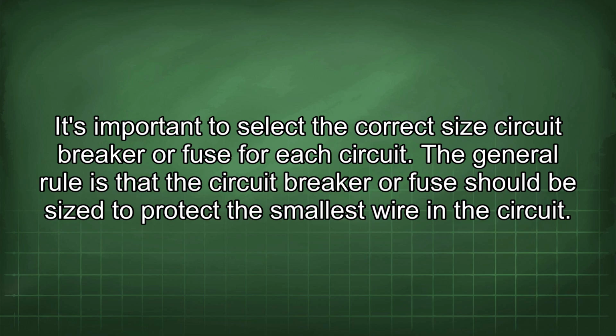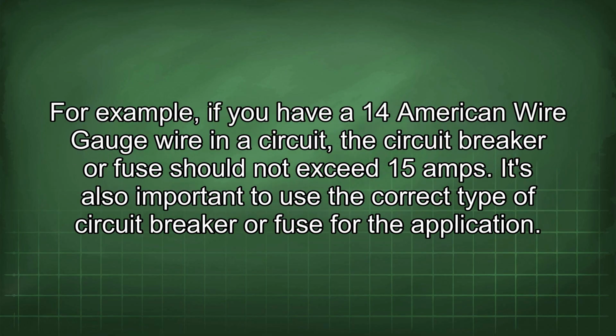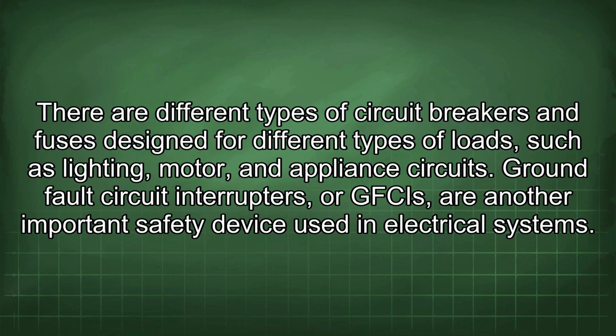The general rule is that the circuit breaker or fuse should be sized to protect the smallest wire in the circuit. For example, if you have a 14 American wire gauge wire in the circuit, the breaker or fuse should not exceed 15 amps. It's also important to use the correct type of circuit breaker or fuse for the application. There are different types of circuit breakers and fuses designed for different types of loads, such as lighting, motor, and appliance circuits.